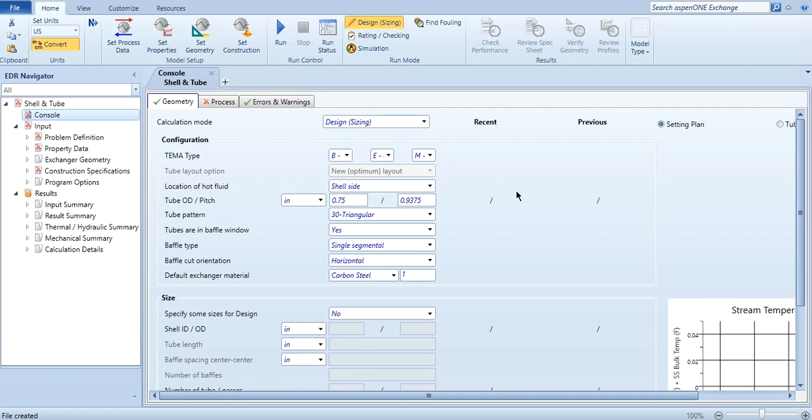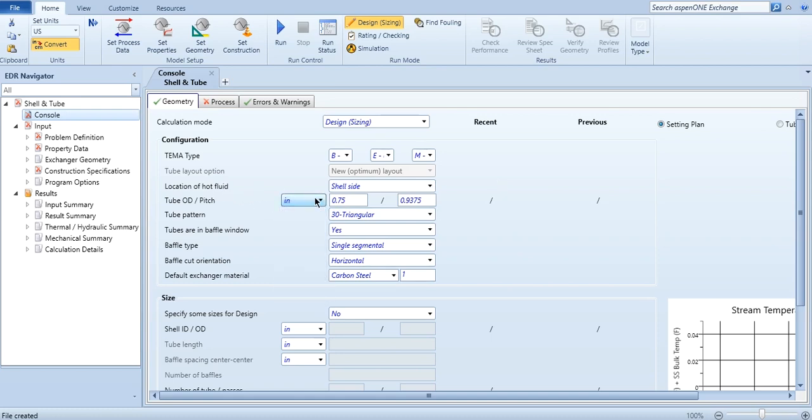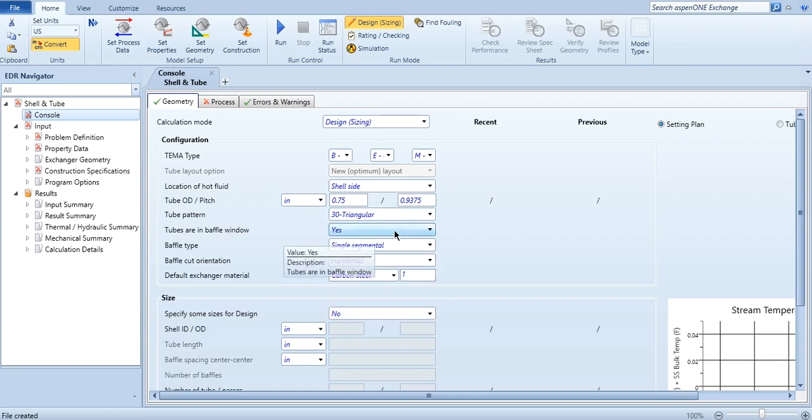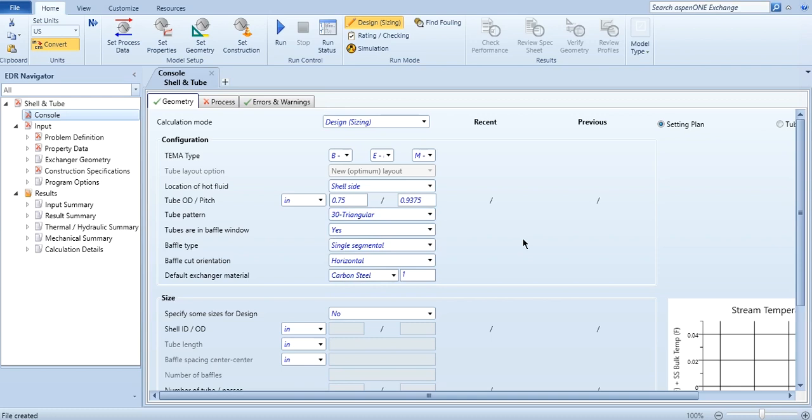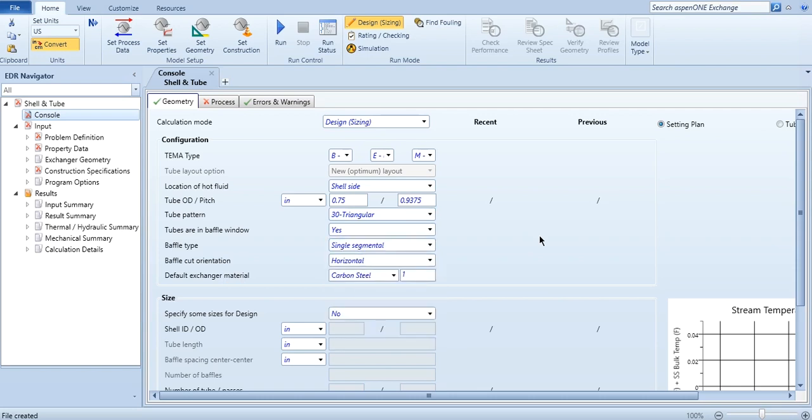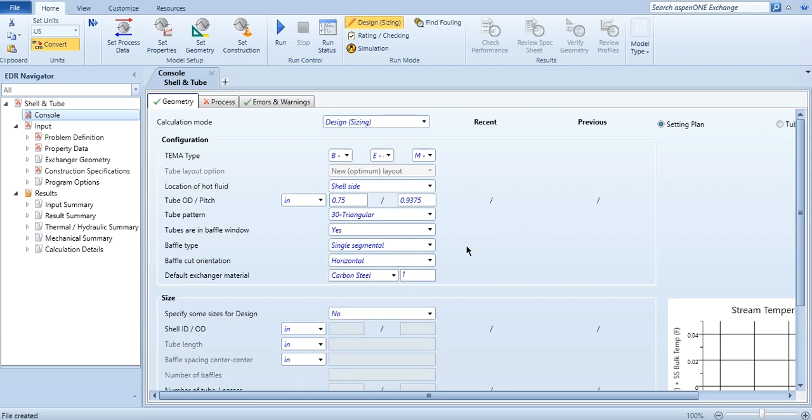Or you can either specify these, or even Aspen can give you the information about it. Then location of hot fluid, usually by default it is shell side, you can even vary it depending on the information available. Then the tube pitch, you can select the unit as per your requirement or desired. Then the tube pattern, either it is 30 degree triangular, 60, 90, 45. Then tubes are in baffle window, yes or no. Then what is the baffle type: single segmental, double segmental, triple segmental. Then the orientation, whether it is horizontal or vertical in the system.